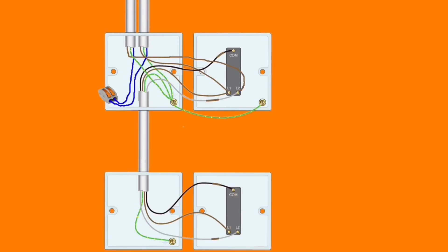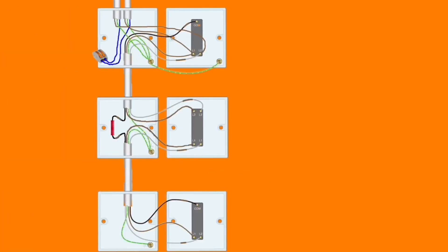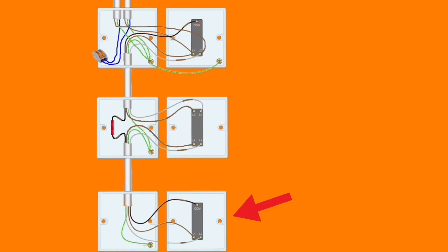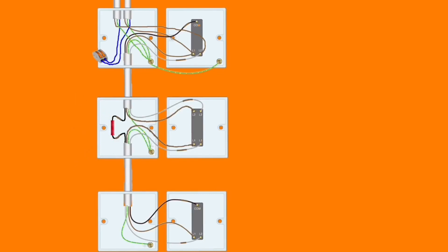For two-way and intermediate switching in the supply-to-switch method, our original switching position is at the top, the second switch down was the two-way from our previous presentation, and we've added an extra cable down to the bottom switch. The top switch is still a two-way switch, the middle switch is now an intermediate switch, and the new bottom switching position is a two-way switch. The connections in the top and bottom switches are identical to those previously discussed. The black conductor within the intermediate switch on both sides of the through crimp is identified with brown sleeving and joined together, with brown and gray conductors from the three-core cables connected in the top or bottom of the intermediate switch accordingly.